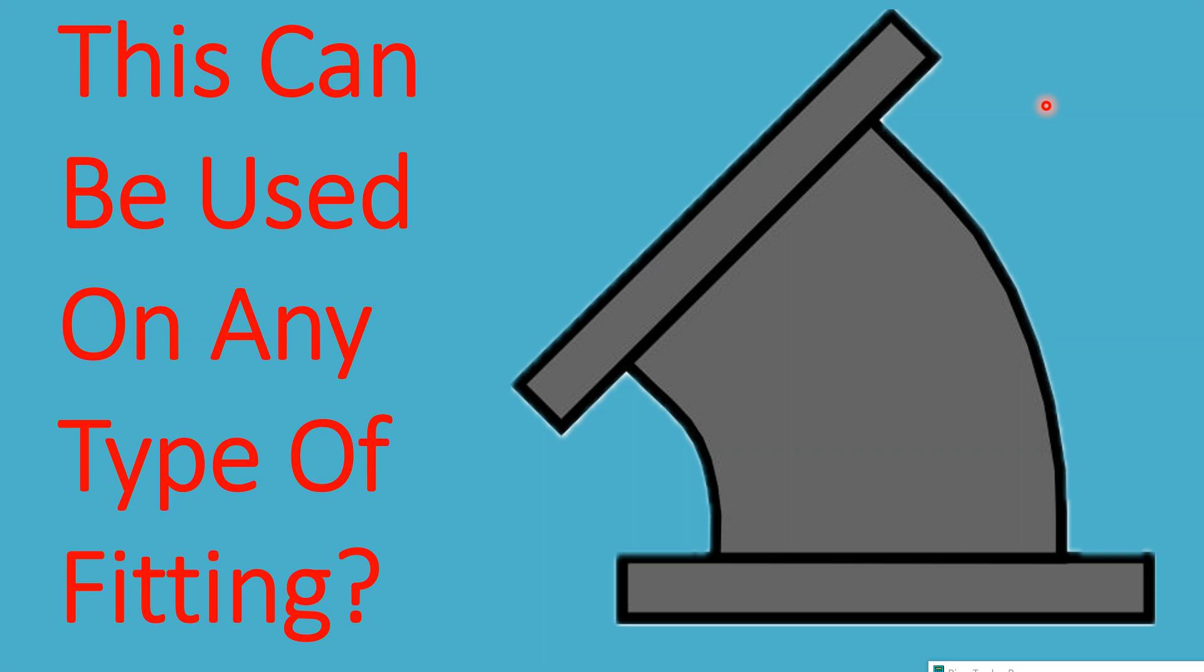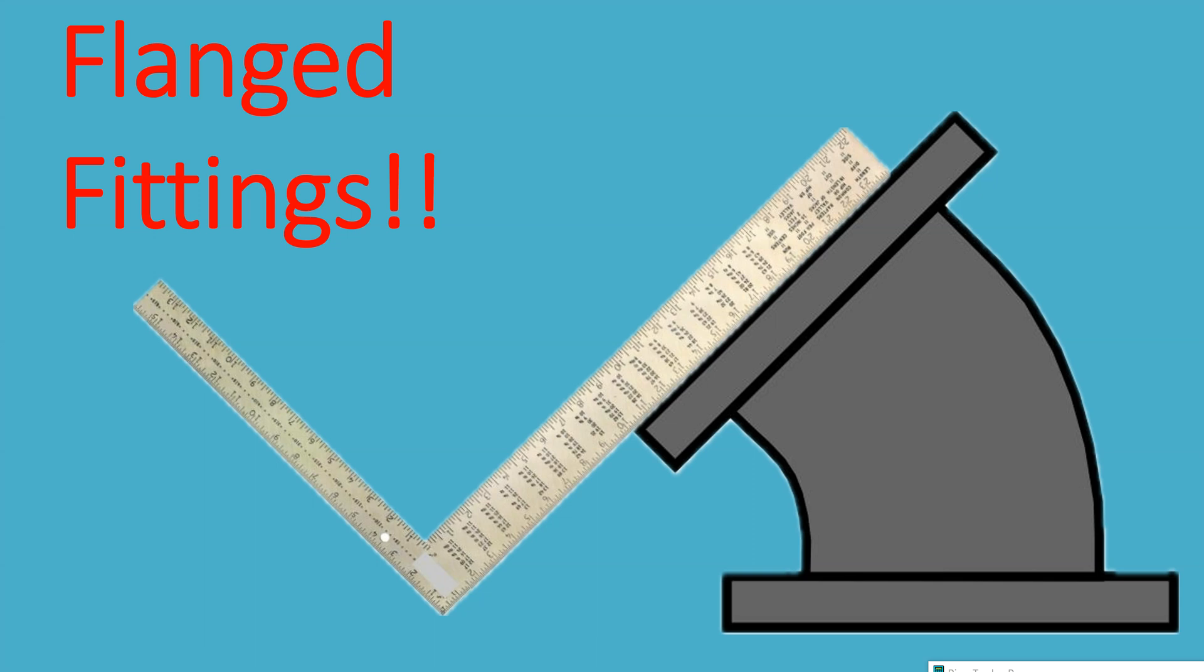You have a flange fitting, maybe a 125-pound flat face. Okay? You can take your square, run it across the face, bring it to the ground, mark it, apply the rules, put the run in, put half the angle of turn in, press offset. That'll give you the fitting takeoff.